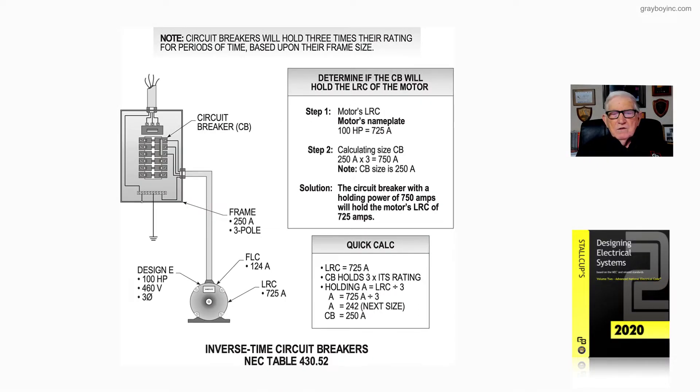This illustration deals with sizing an inverse time circuit breaker to allow a motor to start and accelerate its load. Notice, starting with a note again, an inverse time circuit breaker will hold about three times their rating at 600 volts or less, as a rule of thumb, for a period of time based upon the frame size of the circuit breaker.